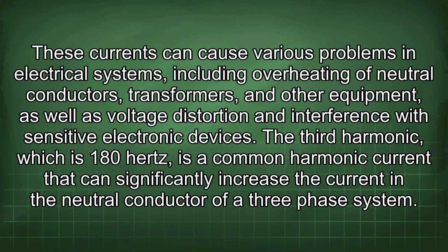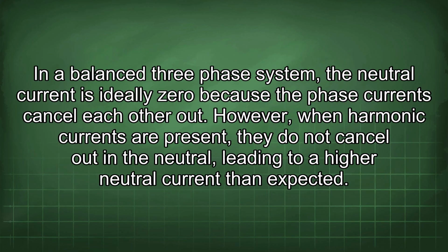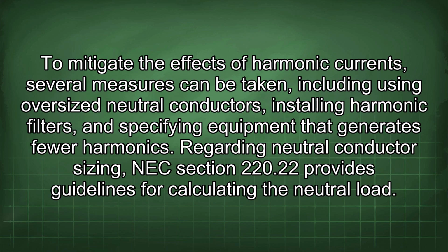The third harmonic, which is 180 Hz, is a common harmonic current that can significantly increase the current in the neutral conductor of a 3-phase system. In a balanced 3-phase system, the neutral current is ideally zero because the phase currents cancel each other out. However, when harmonic currents are present, they do not cancel out in the neutral, leading to higher neutral current than expected. To mitigate the effects of harmonic currents, several measures can be taken, including using oversized neutral conductors, installing harmonic filters, and specifying equipment that generates fewer harmonics.